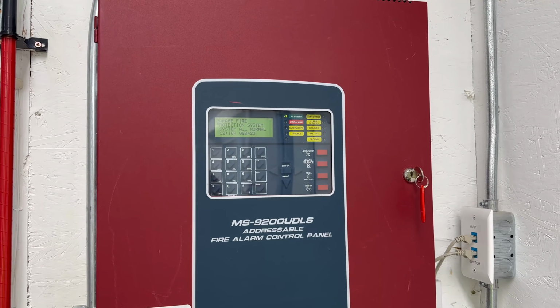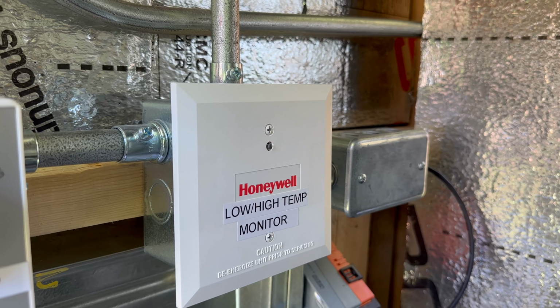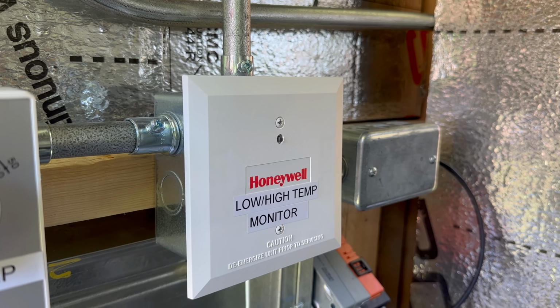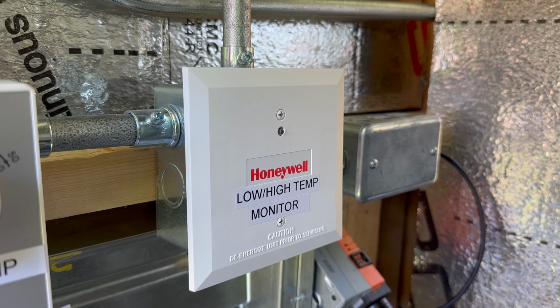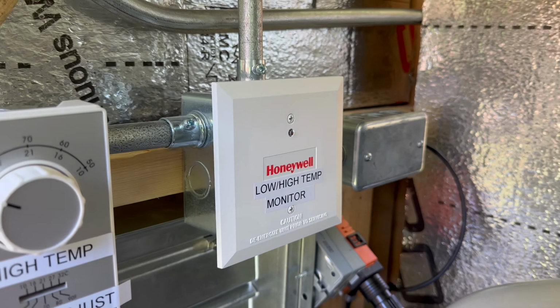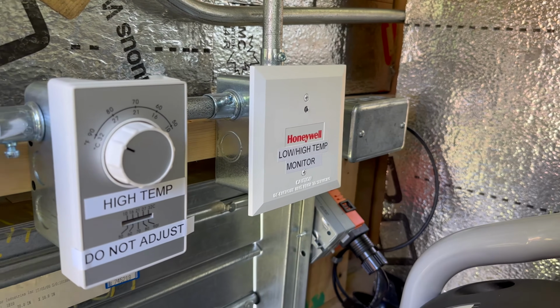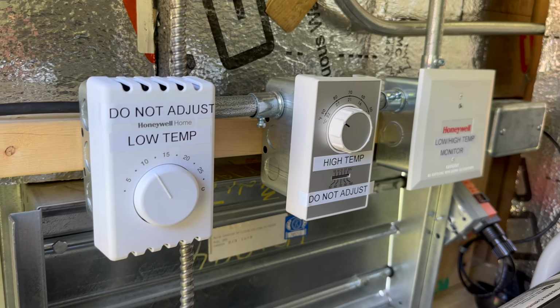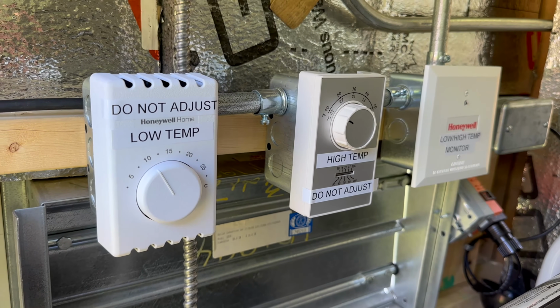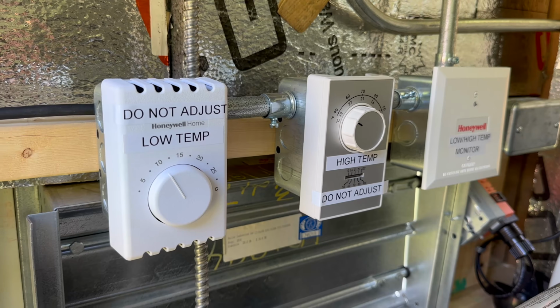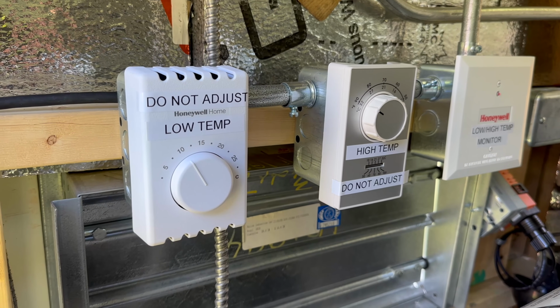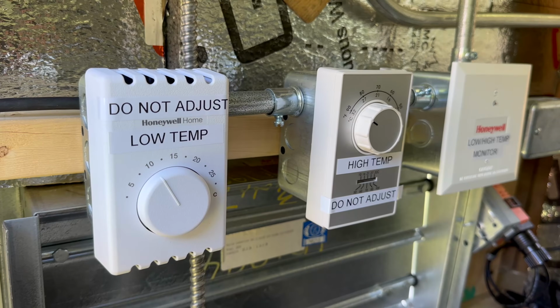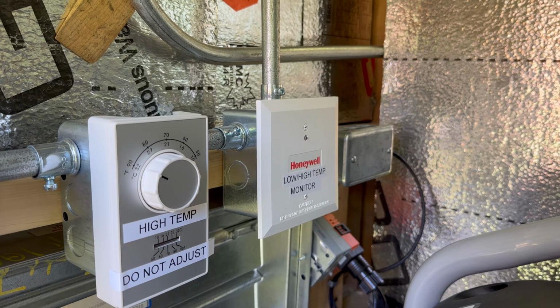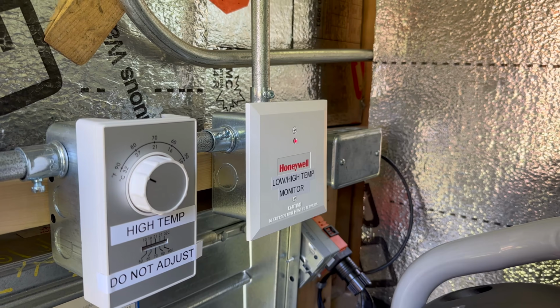I currently am using around 21. 2 of those points are taken up by this module. The reason this one takes up 2 is it is a dual monitor module where it can turn the addressable data logic into conventional zones, which is just 2-wire open or closed circuit, where these thermostats are what ties in to the normally open fire alarm circuits on this module, where if one of those circuits closes, the module will recognize that and tell the panel that that has happened.